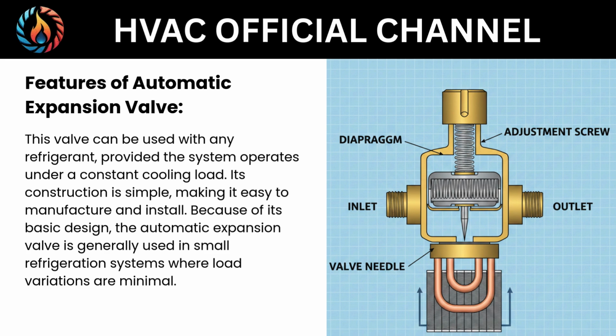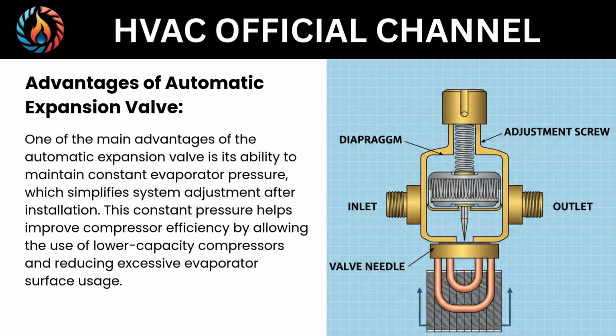Advantages of automatic expansion valve. One of the main advantages of the automatic expansion valve is its ability to maintain constant evaporator pressure, which simplifies system adjustment after installation. This constant pressure helps improve compressor efficiency by allowing the use of lower capacity compressors and reducing excessive evaporator surface usage.